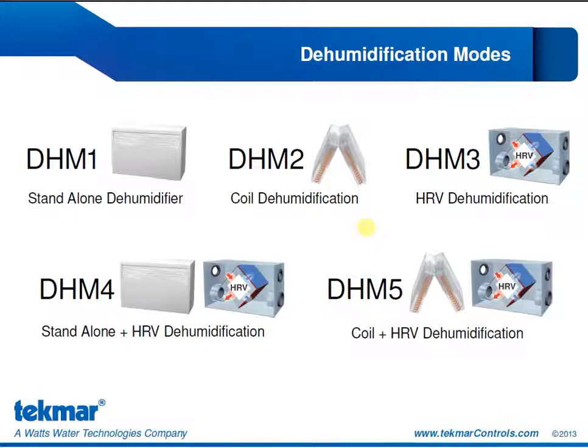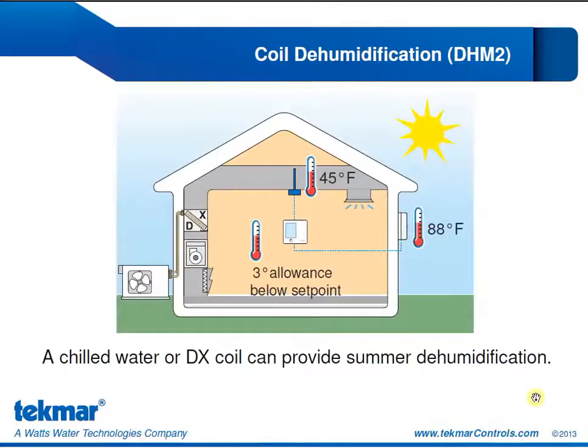Dehumidification mode 4 combines the operation of an HRV with a standalone dehumidifier. And this would be selected if we want to use the HRV when we can, typically in the winter months. And then if we need dehumidification during other times of the year, we could use the standalone unit. Dehumidification mode 5 is a similar concept. We're going to use the HRV when we can, typically in the winter, and then we can use the coil during the other times of the year when we're in cooling mode. So it's kind of the perfect pairing. We have a dehumidifier for cooling mode and one for heating mode.